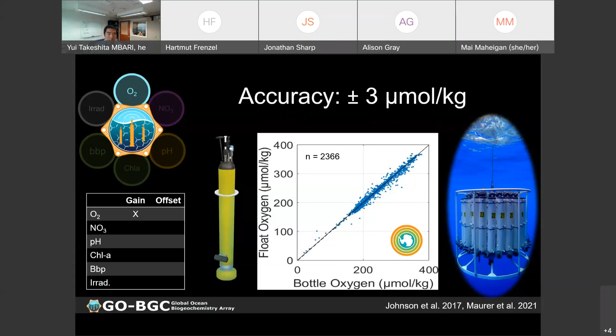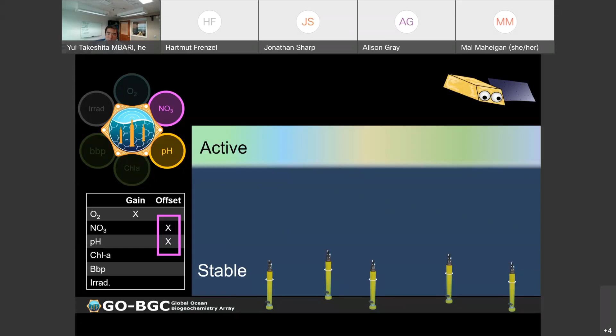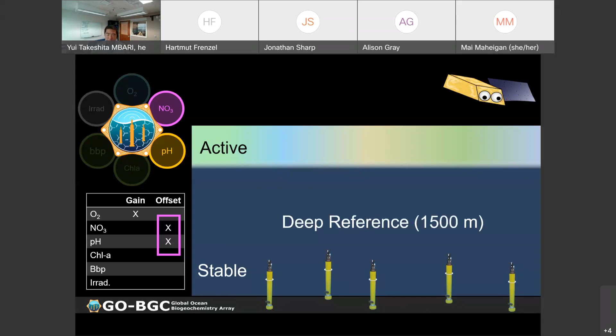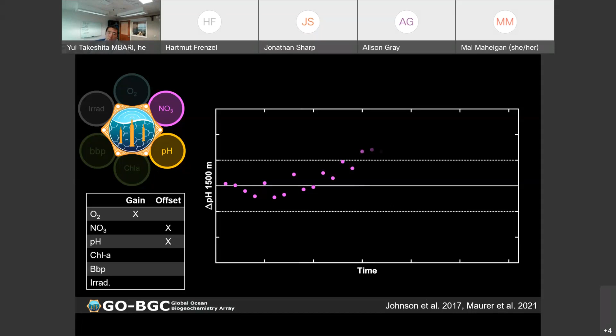Nitrate and pH, I'm going to lump them together because the data adjustment protocol is very similar. For both of these parameters, an offset is applied. We adjust the data based on deep measurements, where the deep ocean has stable pH and nitrate. We predict what this reference field in the deep is by using global algorithms such as the LIR series or CANYON-B. Each time the float goes down to 1,500 meters, we can calculate the difference between the float measurement and the reference pH or nitrate. If it falls between these accepted error bounds, then we don't adjust the data at all. But once it starts drifting outside of the bounds, we apply a piecewise linear regression to correct for this drift and then apply a time-varying offset correction.